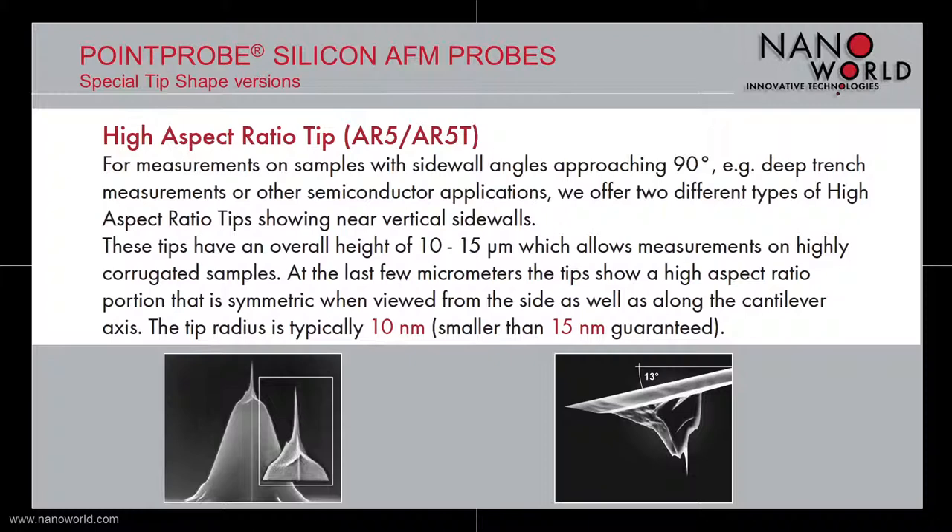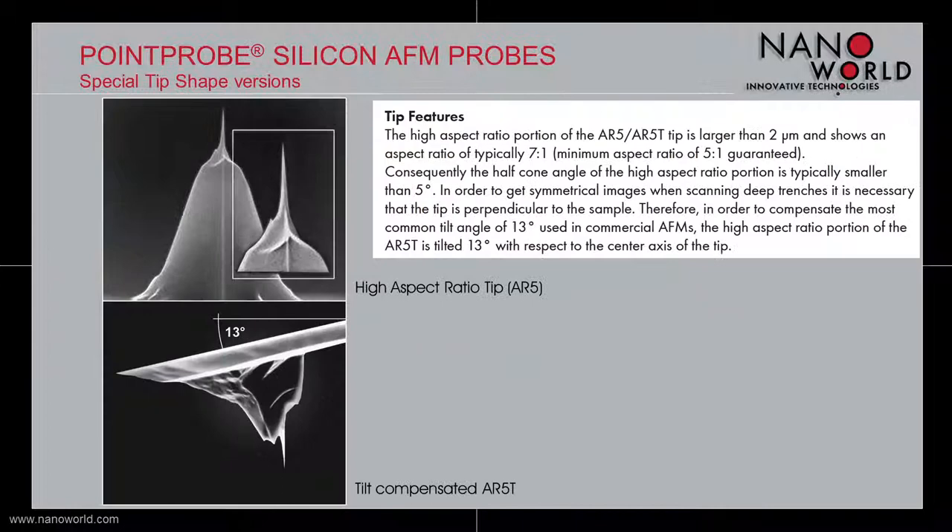The second special tip shape is our high aspect ratio tip. This tip is designed for measurements on samples with sidewall angles approaching 90 degrees or other semiconductor applications. The tips are 10 to 15 µm high with a high aspect ratio portion at the last few micrometers of the tip. The tip radius is typically 10 nm, and we guarantee a radius smaller than 15 nm. The high aspect ratio portion is larger than 2 µm with a typical aspect ratio of 7 to 1, and an aspect ratio of at least 5 to 1 is guaranteed.